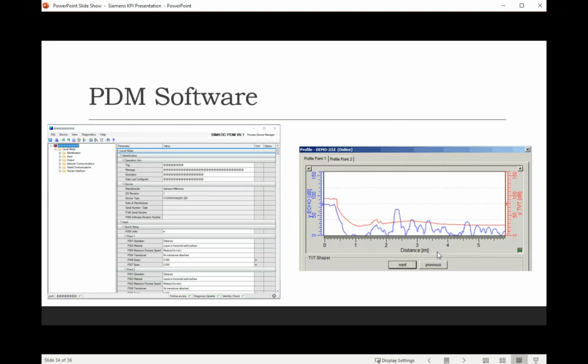All right, I'm going to touch base real quick on PDM software. PDM software is a program provided by Siemens. It's a $120, $130 per license software, and it allows you to access the Hydroranger 200 using your laptop or computer through the Modbus port on the Hydroranger. Where this is really useful is with those older style Hydrorangers where it's parameter driven. You can connect to it with your laptop, download the parameters from the Hydroranger onto your laptop, make any changes you need to make, and then re-download into the Hydroranger. That way you don't have to pull up a manual in order to make any changes.